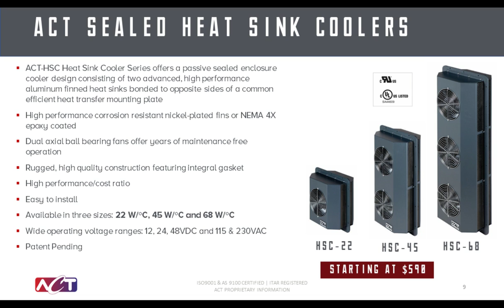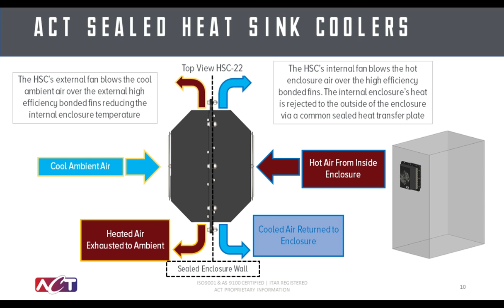To go further into how these types of solutions operate, first we'll take the inside of the enclosure portion. The HSC's internal fan blows the hot enclosure air over the high-efficiency bonded fins. The internal enclosure's heat is rejected to the outside of the enclosure via a common sealed heat transfer plate. On the external portion of the HSC model, the external fans blow the cool ambient air over the external high-efficiency bonded fins, reducing the internal enclosure temperature.